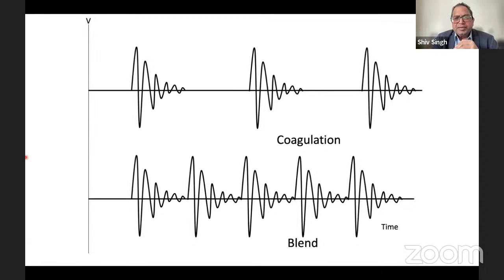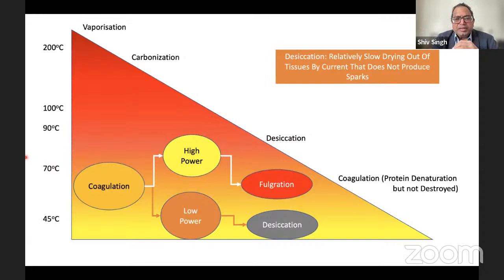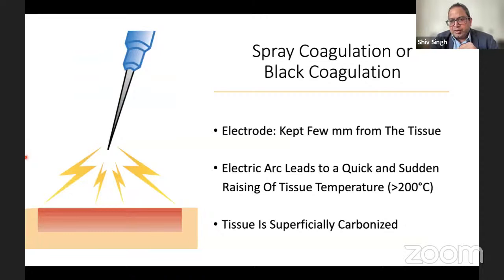Coagulation can be at low power and high power. When coagulation is used at low power, it causes desiccation. Desiccation is basically slow drying of the tissues. Whereas if you use high power, it causes fulguration. In fulguration, you can have the diathermy probe away from the skin and the current will flow through it. It's called sparking. This is also known as spark coagulation or black coagulation. You don't have to touch the skin. It'll cause an electric arc, leading to a quick and sudden rise of temperature, more than 200 degrees Celsius, and the tissue is superficially carbonized. And that's why it's called black coagulation as well.